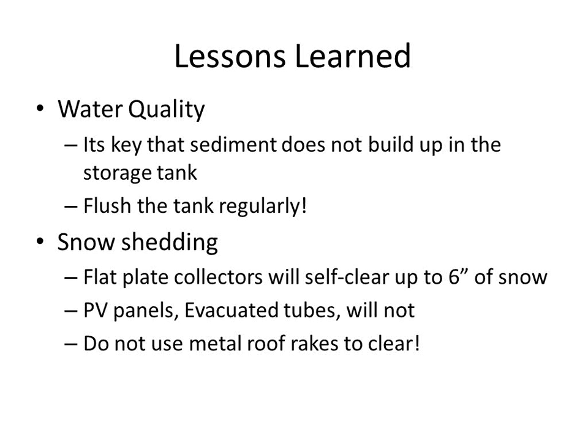Because as soon as sediment builds up in the storage tank, particularly in a thermal siphoning system, you're going to stop the thermal siphoning action and the system simply won't work. Whereas on a fossil fuel or electric water heater, the system still works, you just get less and less capacity over time. So it's critical that they're flushed.